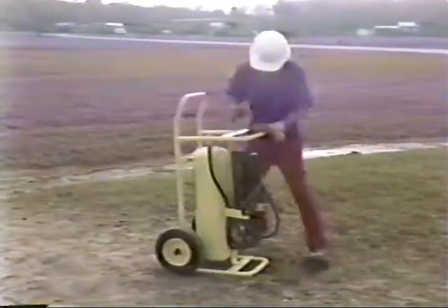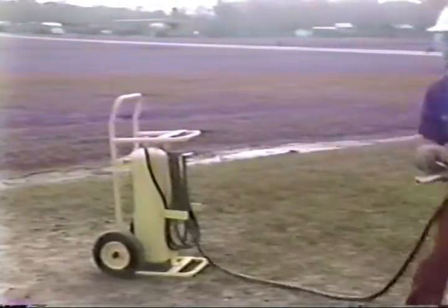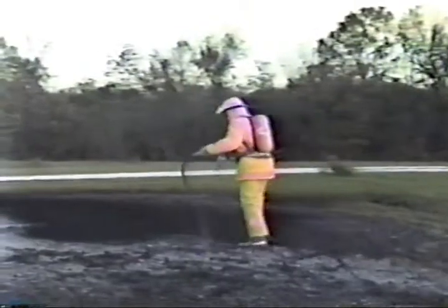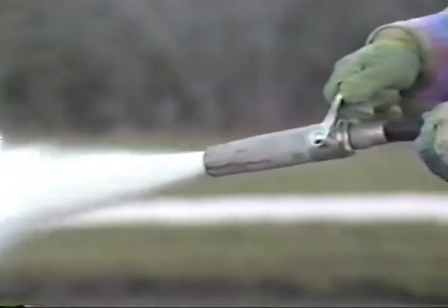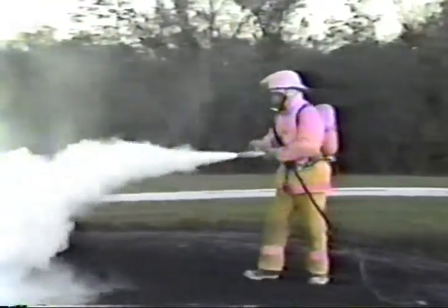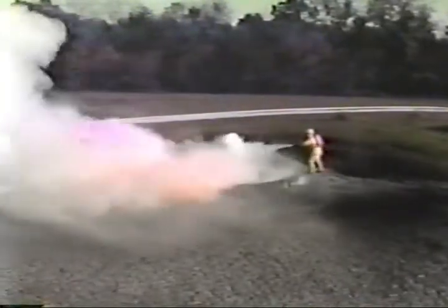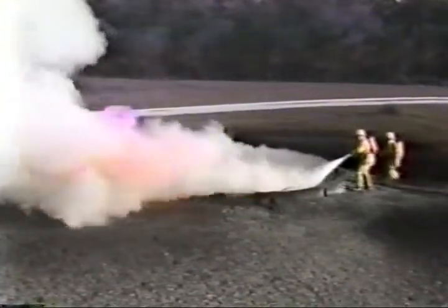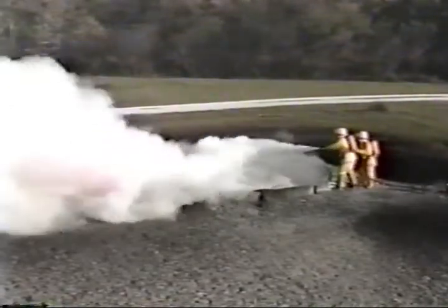Larger firefighting applications may require wheeled extinguishers, which are available in many sizes and with a variety of agents. Wheeled extinguishers have an operating range of up to 40 feet and empty in anywhere from 30 seconds to 2.5 minutes. Yet while these devices have a much greater range, they're also more difficult to use and require thorough training. A fire large enough to require this type of extinguisher is dangerous. If you are not sure of your capability or you don't know how to operate the extinguisher, leave the firefighting to trained firefighters.